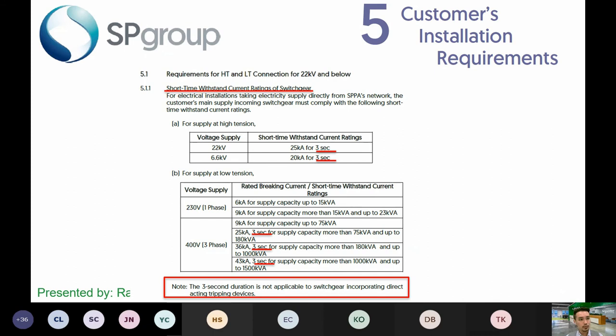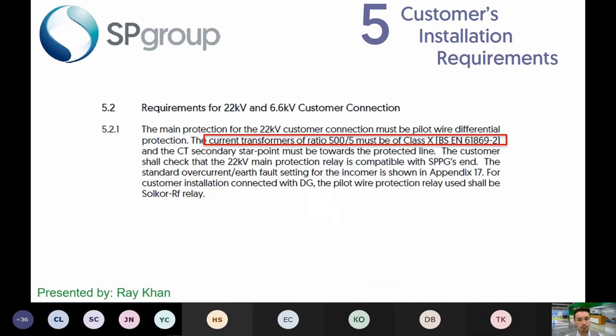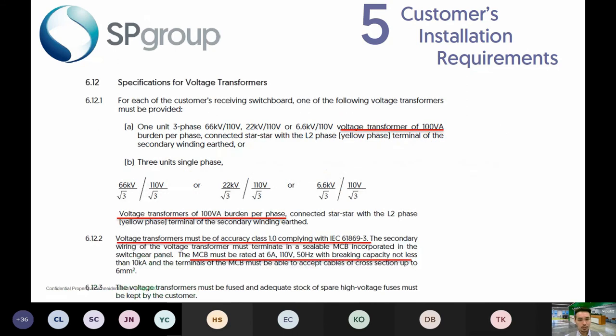All right. So for 6.6 kV as well, it's 20 kA for 3 seconds. Right. So next it also talks about the CT, the current transformer ratio at 500/5. So 500 is the primary winding, 5 is the secondary winding. So that is basically converting from a 500 amp maximum to a 5 amp. All right, so here it talks about the VT burden at 100 VA, which is sufficient as per the minimum requirement indicated in here. So it's 100 VA.